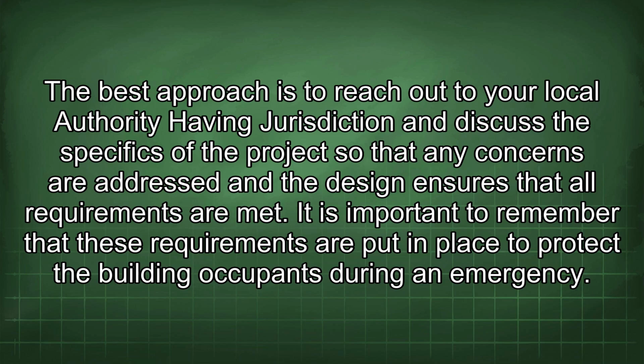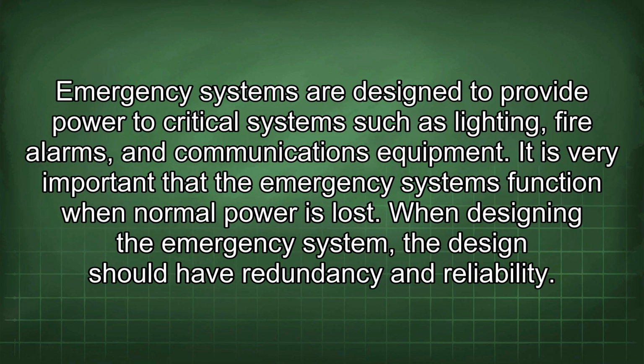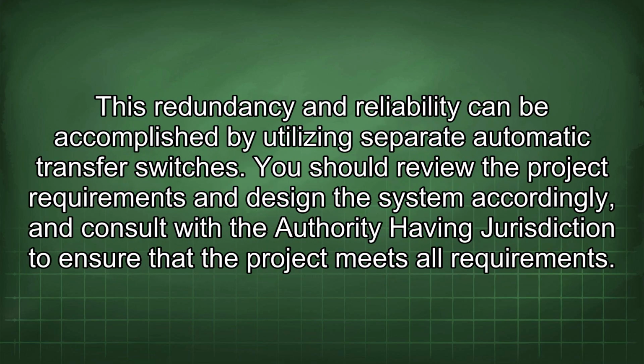It is important to remember that these requirements are put in place to protect the building occupants during an emergency. Emergency systems are designed to provide power to critical systems such as lighting, fire alarms, and communications equipment. It is very important that the emergency systems function when normal power is lost. When designing the emergency system, the design should have redundancy and reliability. This redundancy and reliability can be accomplished by utilizing separate automatic transfer switches. You should review the project requirements and design the system accordingly, and consult with the authority having jurisdiction to ensure that the project meets all requirements.